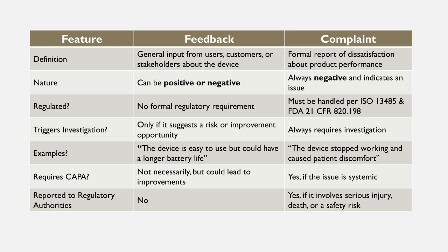But complaints in themselves, absolutely 100% must be handled per how ISO 13485 dictates, or within the US, how FDA Title 21 Part 820, subsection 198, dictates. Now, feedback in itself doesn't trigger an investigation, unless it seems to suggest a risk or an improvement opportunity, but complaints 100% always require investigations within the company.